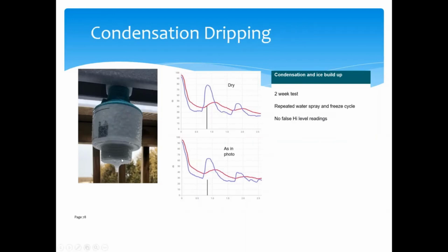Let's talk a little bit about condensation dripping. With ultrasonic or radar, there are different things we could do here. With ultrasonic, we have that self-cleaning face that helps get the condensation to vibrate off the face of the transducer. We can also spray the face with Rain-X and put it at a very slight angle, maybe a degree or two, and allow the condensation to bead off. As you can see in this photo, we sprayed this unit with condensation, allowed it to freeze on there, and we could still get a good level measurement.